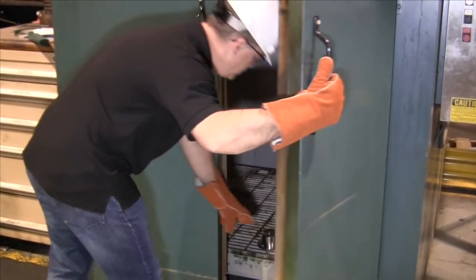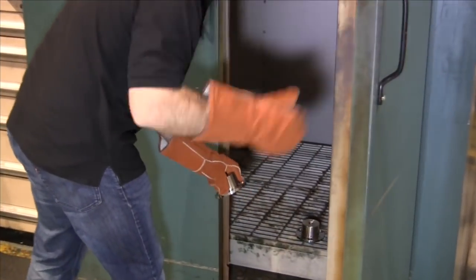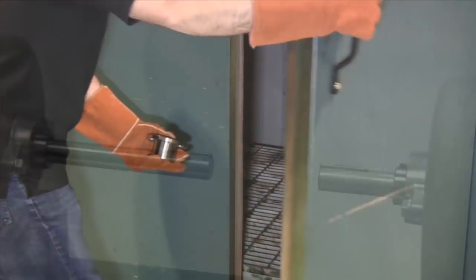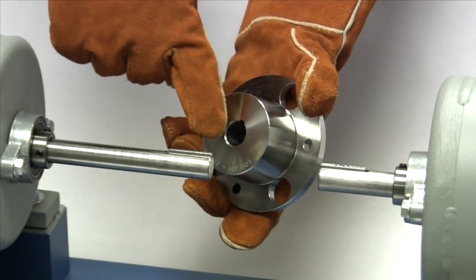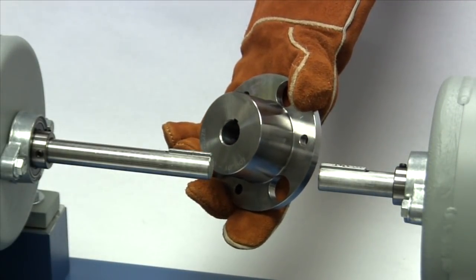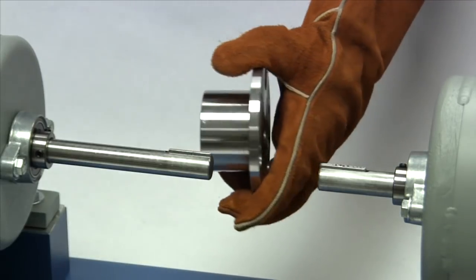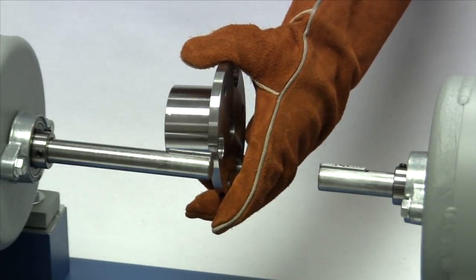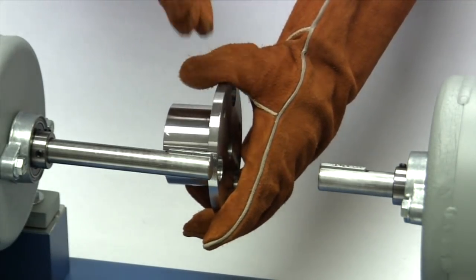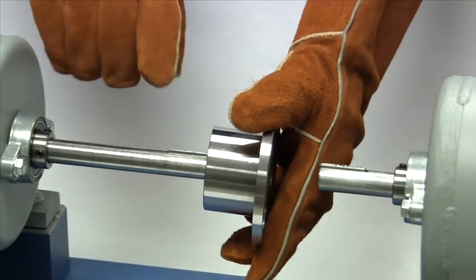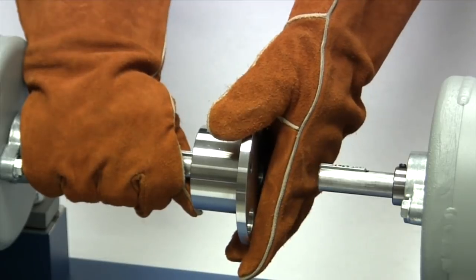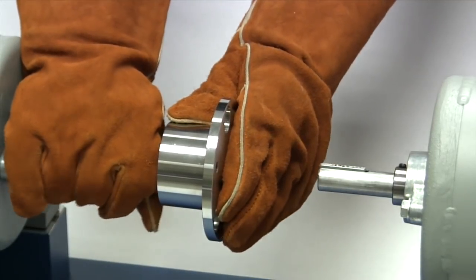When the hubs reach the recommended temperature, the bores will be expanded enough to provide a few thousandths of clearance when sliding the hubs onto the shafts. Make sure each hub is oriented with the flanged end of the hubs facing the end of the shafts. The keys should already be in place in the keyways and the hubs should slide onto the shaft with little or no difficulty. Each hub will start cooling down right away and you will need to work quickly and accurately to position the hubs on the shafts.